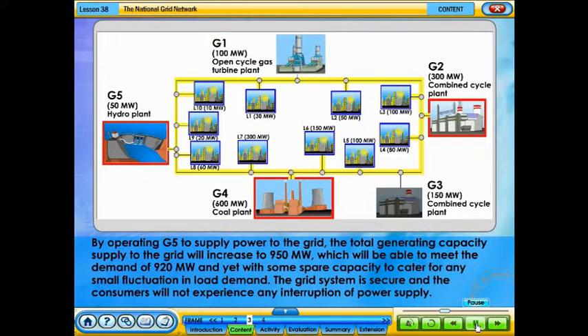By operating G5 to supply power to the grid, the total generating capacity supplied to the grid will increase to 950 megawatts, which will be able to meet the demand of 920 megawatts, and yet with some spare capacity to cater for any small fluctuation in load demand. The grid system is secure, and the consumers will not experience any interruption of power supply.